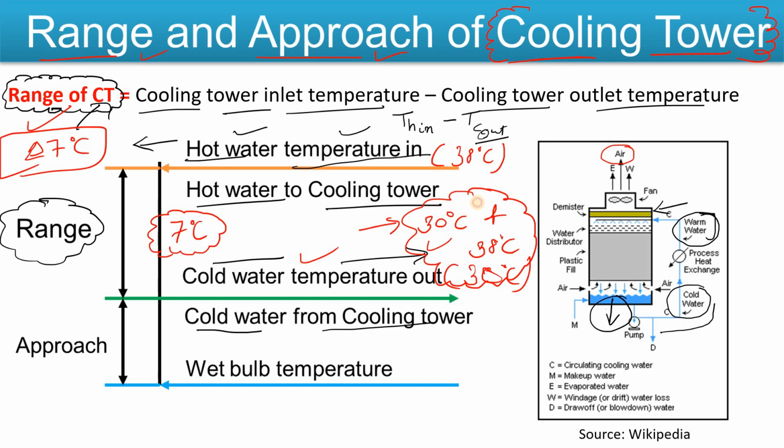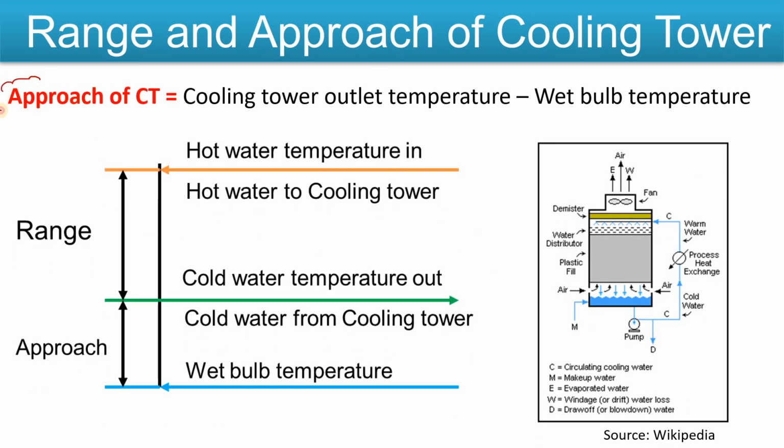What is the approach of the cooling tower? Basically, the approach of the cooling tower is the cooling tower outlet temperature minus the wet bulb temperature. Okay, so first of all, let's discuss the cooling tower outlet temperature. What is that? That is your cooling tower outlet temperature, meaning cold water temperature, right?